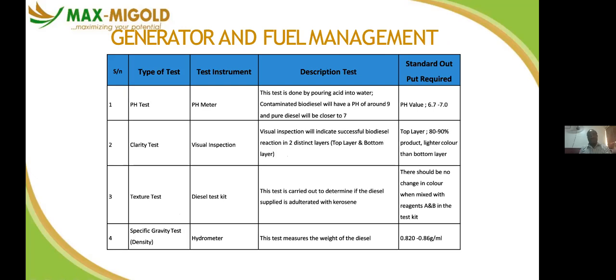This is the value for the pH test. We have a range between 6.7 and 7.0, that's the pH test. We have the clarity test, it must be 80 to 90%, based on the color of the diesel. If it's too white, it's not okay, and if it's too dark, it's not okay. That's why a range has been set for this. Then we have the texture test. This test is carried out to determine whether the diesel supply is adulterated with kerosene or not. There should be no change in color when mixed with reagents A and B in the test kit.